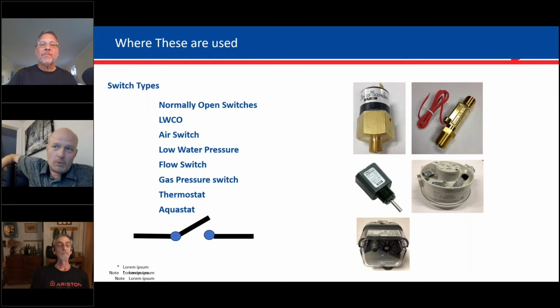So, all right, guys. Where are some normally open switches that NTI uses in its various products? David, you have some historical pictures here. So we've got the Nason water pressure switch. It's a normally open switch that closes with the addition of enough pressure. Now we do call that a water pressure switch, but in reality, it's just pressure, and we'll talk about that in a second. We've got the old NTI flow switch, the GEMS FS380.